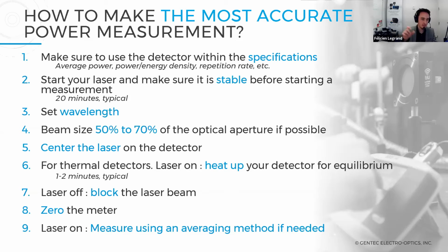Then set the wavelength in the display that you're using. Then, once again, use a beam size between 50 and 70% of the optical aperture if possible, whether you're using the natural divergence of the beam or using an expander. Then center the laser on the detector. That will help for repeatability.